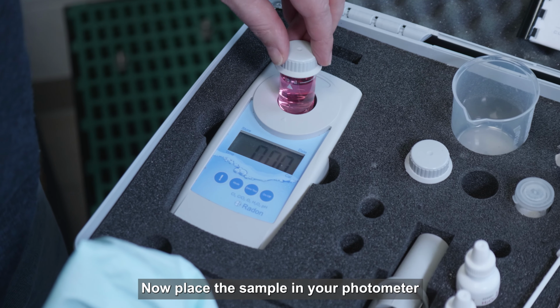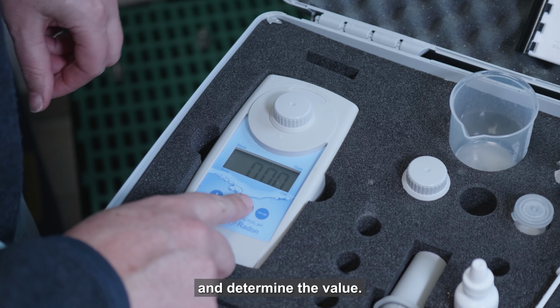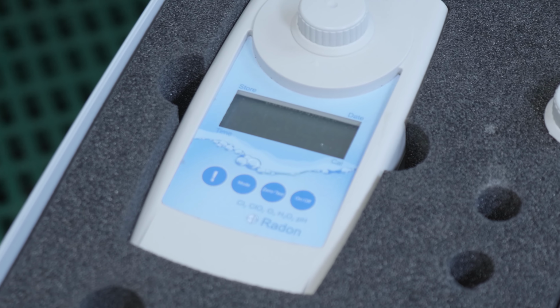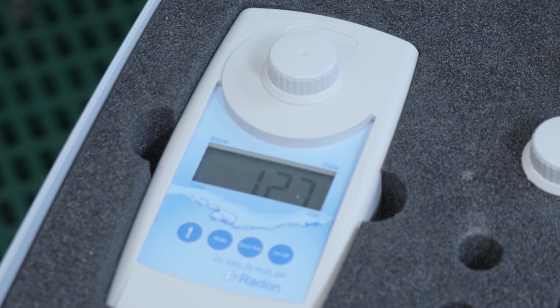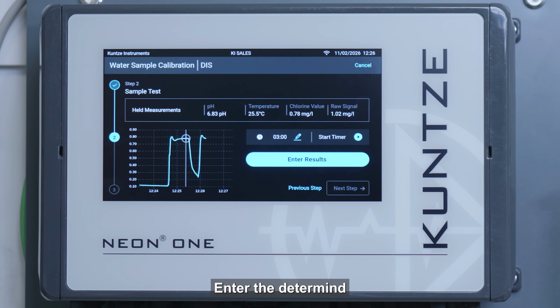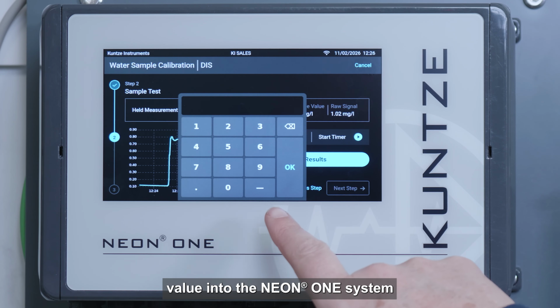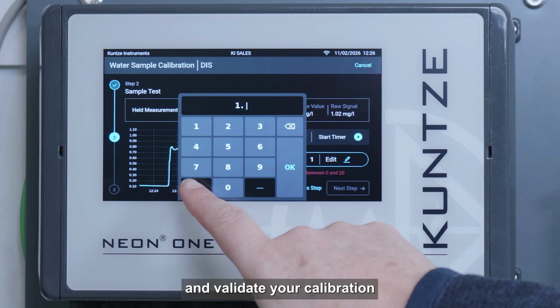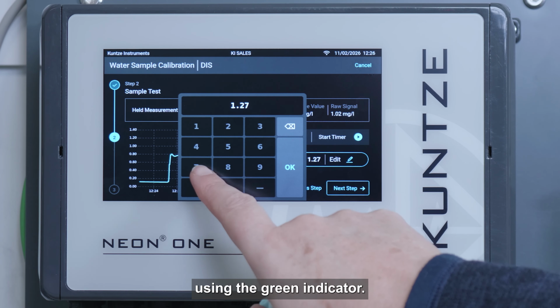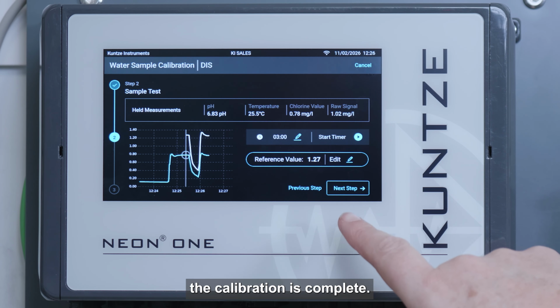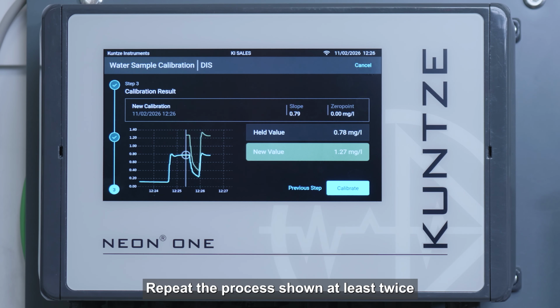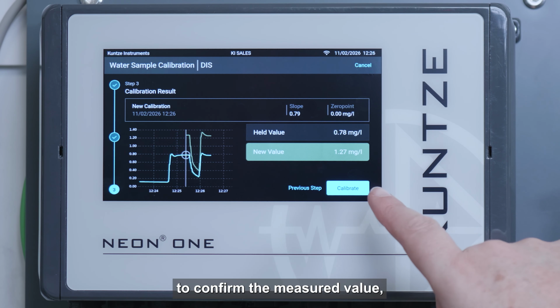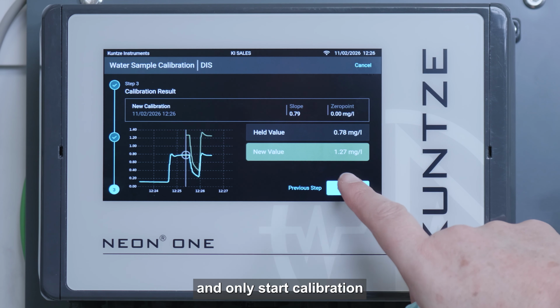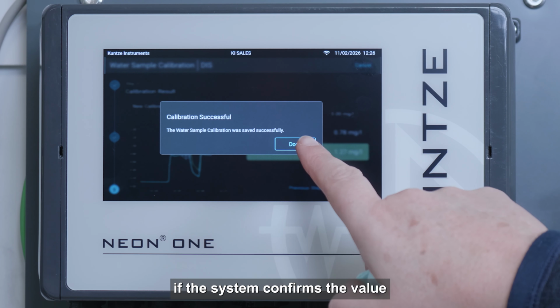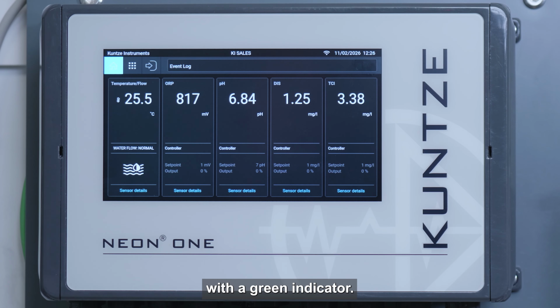Now, place the sample in your photometer and determine the value. Enter the determined value into the Neon One system and validate your calibration using the green indicator. Once this is done, the calibration is complete. Repeat the process shown at least twice to confirm the measured value, and only start calibration if the system confirms the value with a green indicator.